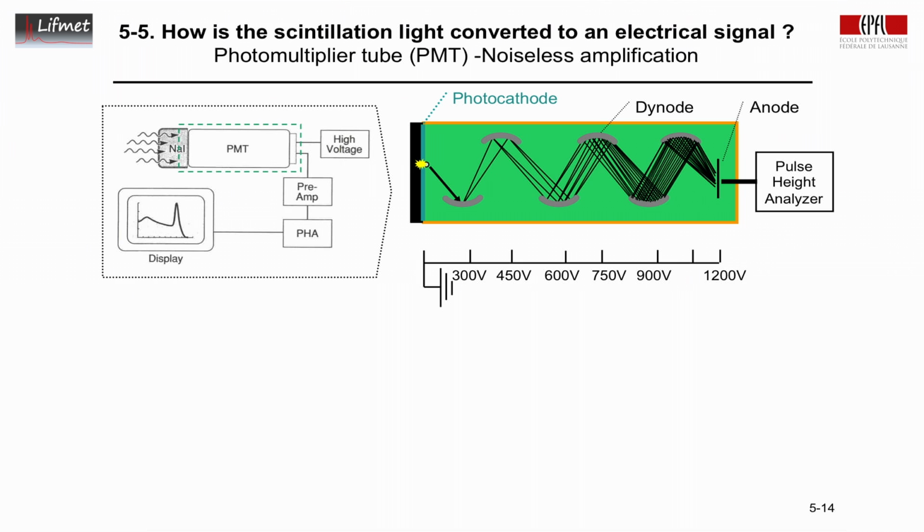So this process essentially allows us from more or less a single photon here to produce a measurable signal of many electrons, that we can measure the change in the electrical signal of those electrons when they arrive at the final anode of the photomultiplier tube. And this is actually technology from more than half a century ago. It is providing virtually noiseless amplification of the signal.